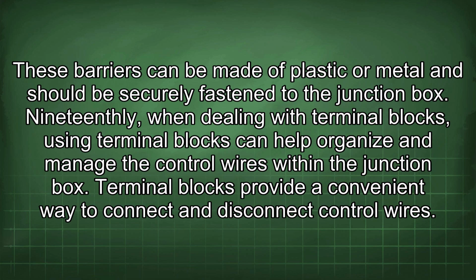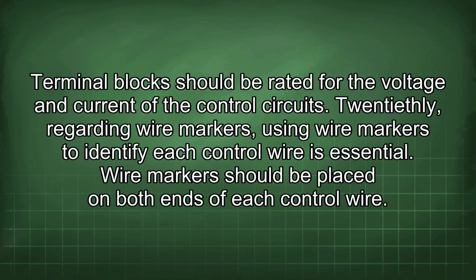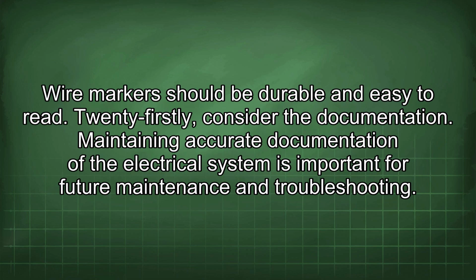19thly, when dealing with terminal blocks, using terminal blocks can help organize and manage the control wires within the junction box. Terminal blocks provide a convenient way to connect and disconnect control wires. Terminal blocks should be rated for the voltage and current of the control circuits. 20thly, regarding wire markers, using wire markers to identify each control wire is essential. Wire markers should be placed on both ends of each control wire. Wire markers should be durable and easy to read.